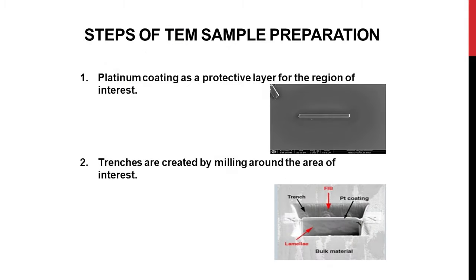The next module is TEM sample preparation. There are different steps — let us go through each. When you prepare a sample for TEM, we make a very thin slice in the order of less than 100 nanometers. To make a lamella for TEM, we need to protect the region of interest. The first step is platinum coating: in-situ we do a deposition of a very thin layer of platinum as a protective layer for the region of interest.